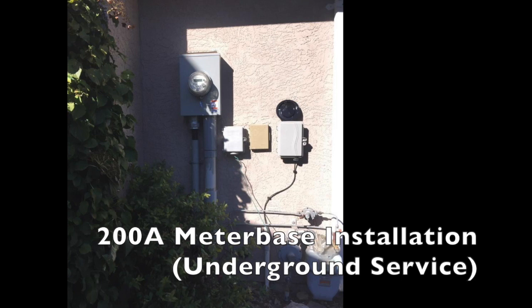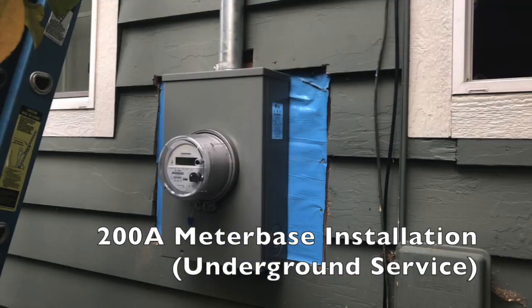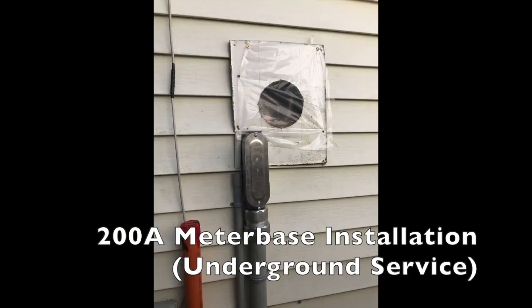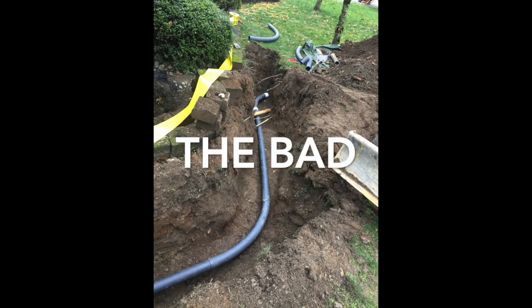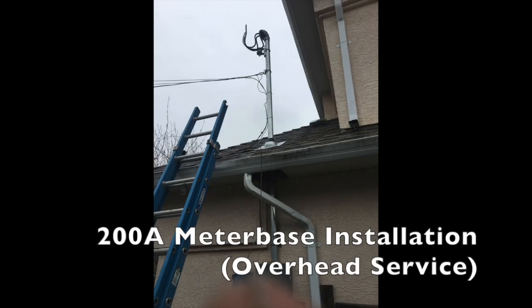Things to know beforehand is sometimes there is a bit of damage that's done from replacing the meter base from 100 amp to 200 amp meter base. We try our best to reduce the amount of damage done to the inside and outside of the home, but in some cases it's unavoidable. Although underground services are easier to complete than overhead services, sometimes issues do arise. An example is in this picture where a pinched duct from the hydro line prevented our new 200 amp cable from being entered into our new meter base. With access to the original duct, we can repair the crushed pipe and install new pipe so the new feeds can be installed.